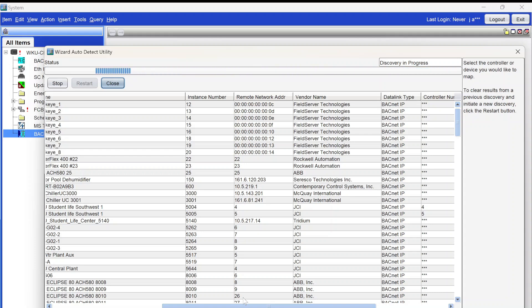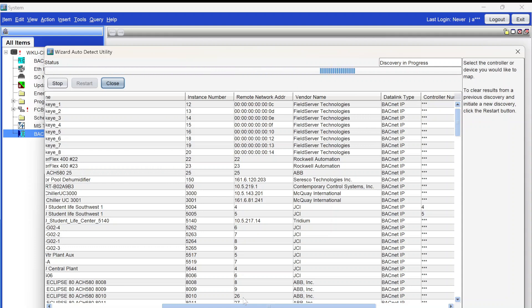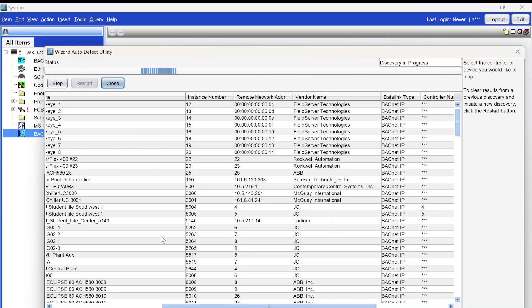For those of you guys who are curious, they do a real good job on this, getting the system set up. And we basically upgraded from an old pneumatic system that was in this building to the new DDC controls. Of course, with the Jace being at the head end of that system. And then we're going to be pulling the devices in from that Jace into Metasys.